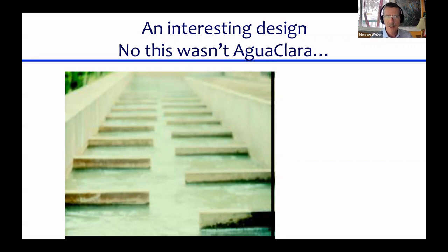Can you describe what caused this to show up in their design? Yeah, their H/S ratio is too small. It was actually less than 2. And so there's no overlap. We wanted something like this where the water was forced to go around the bend, and instead we have this.